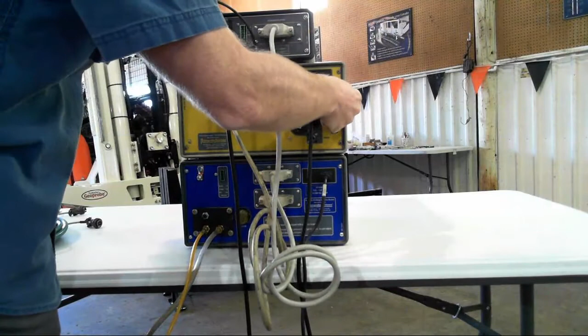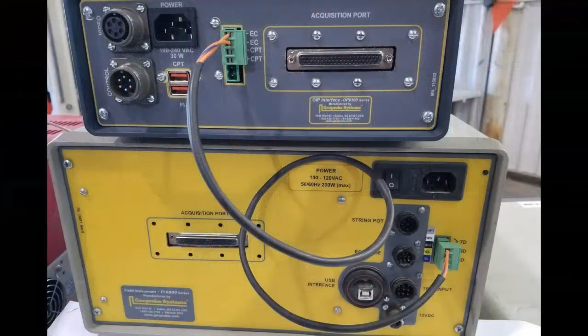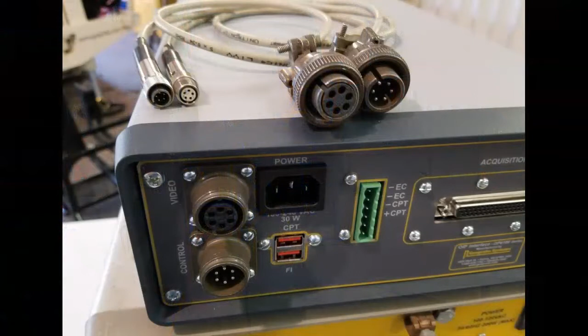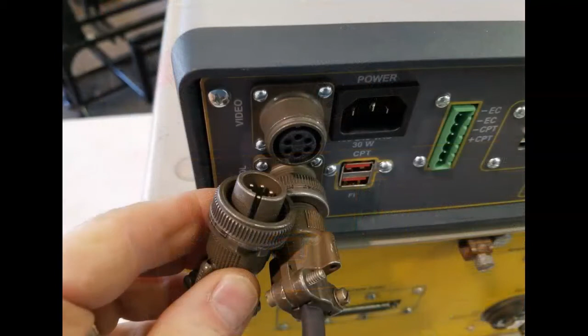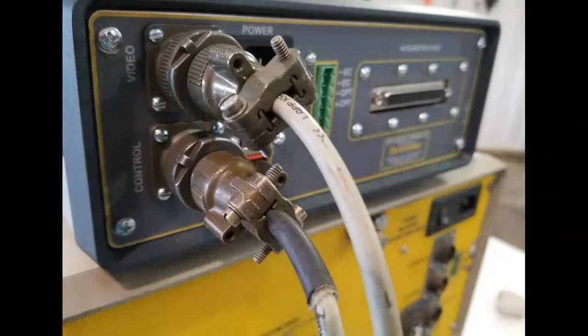We will now link the electrical connectivity connections between the field instrument and the OIP interface with a cable connector. Make sure the wires are in the top two positions of both green terminal connections. These next cables are gender specific to connect the trunk line electrical wires to the OIP interface. The lower connection is the control line for the probe LED and camera, and the upper connection is the video feed return. When you make the connection, press in, then spin the collar and repeat until the fitting is secure.